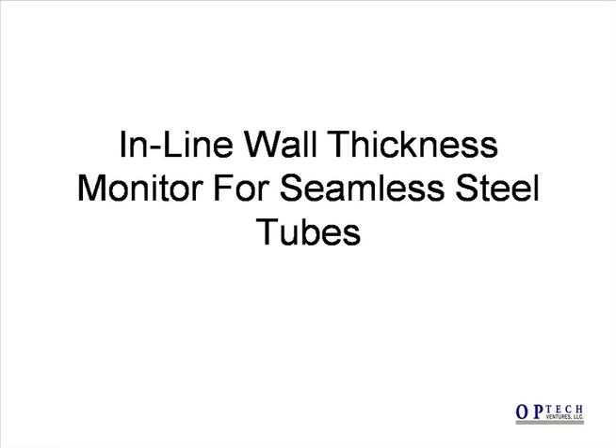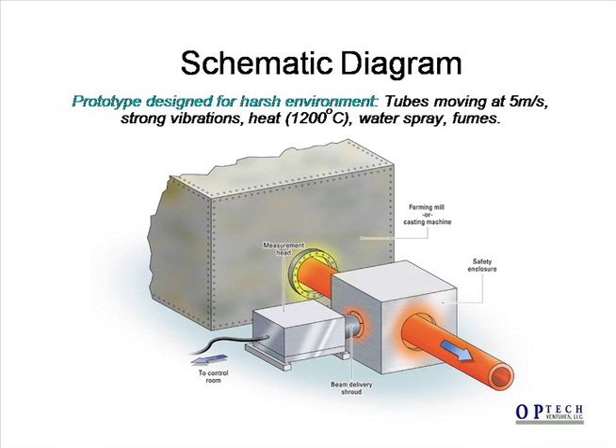The first application is an inline wall thickness monitor for seamless steel tubes. The requirement was to monitor the wall thickness of hot tubes as they exit a forming mill. A measurement head containing both lasers is placed alongside the tube as it exits the mill. Both laser beams are directed to the tube surface, and a shroud surrounds the measurement position for the purpose of eye safety.